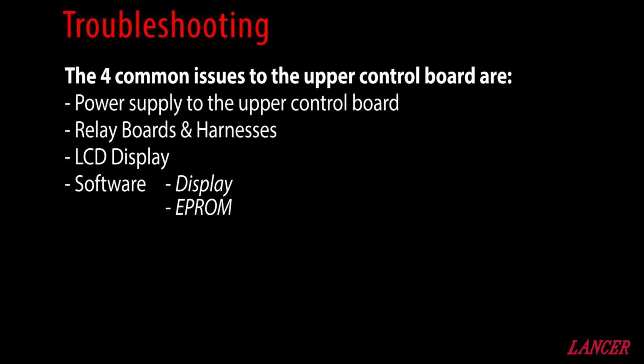Having reviewed the onboard hardware and the connectivity to peripheral hardware, we need to also look at software. It's very easy to replace components before spending time looking at software diagnosis. The four most common areas that we'll review that can cause an issue with an upper control board are the power supplies, the relay board and harness, the display, and then the software. The key here is to make sure to understand the fault first before replacing parts.